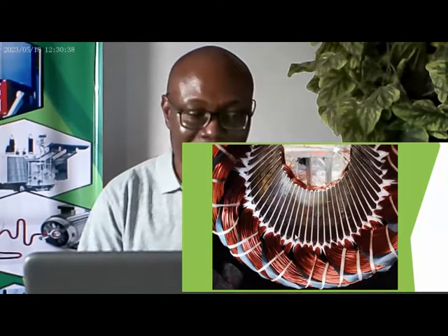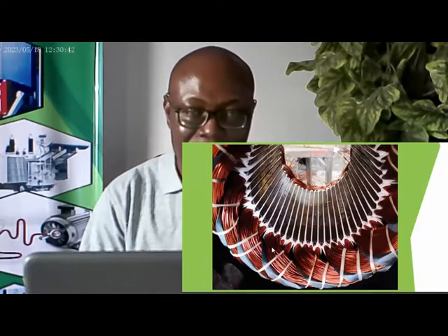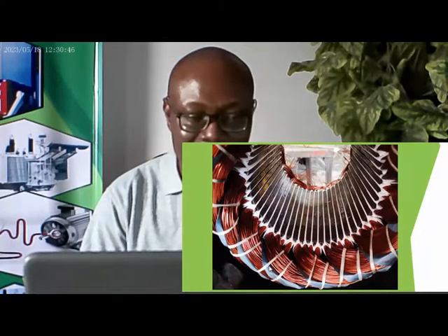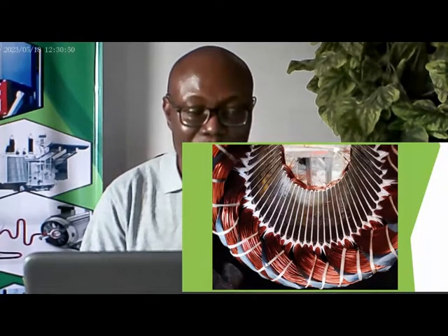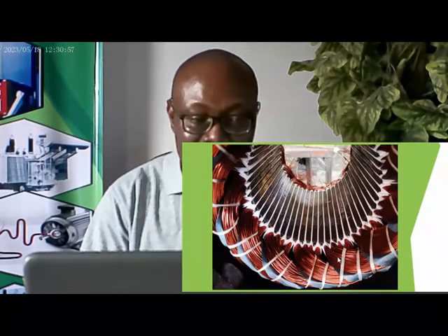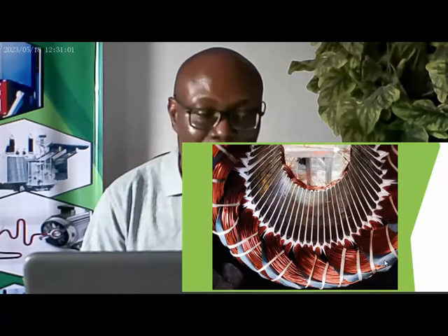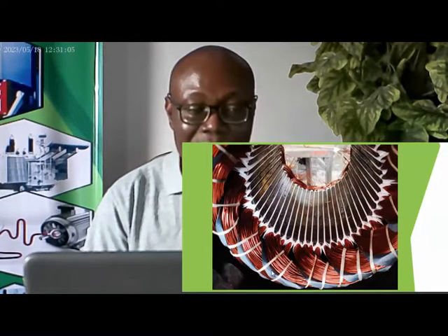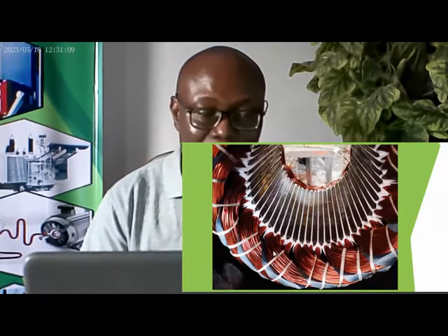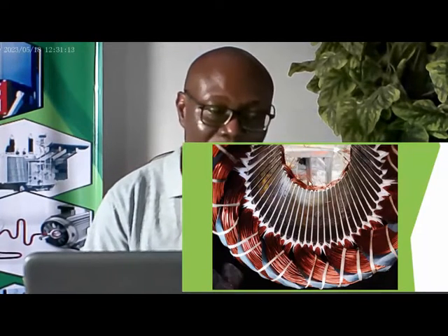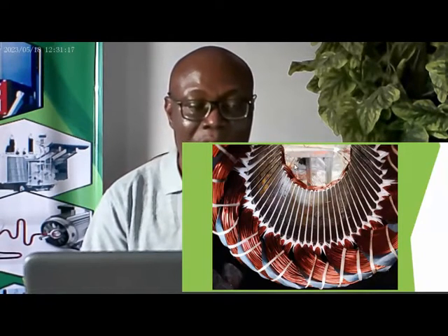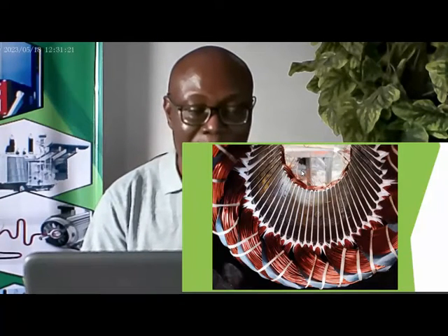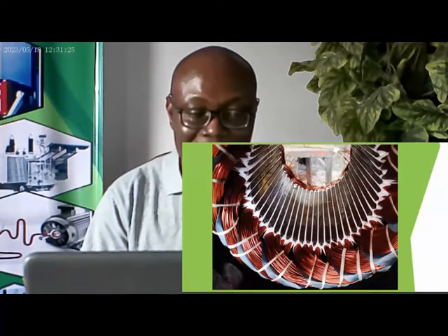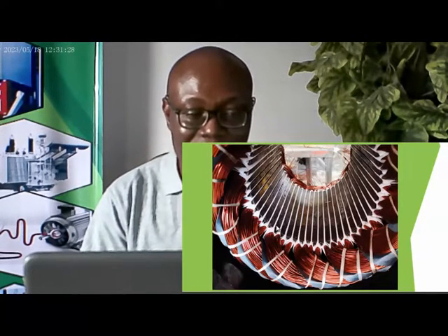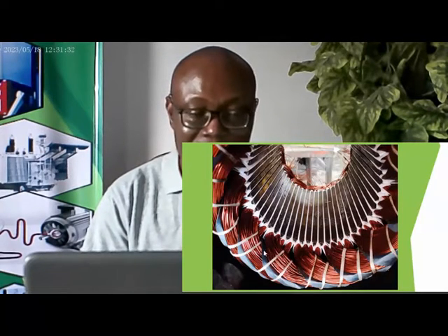If you also look at these windings, you see that there is an insulation, paper lead thread, that is used to separate each of these windings. So this winding does not have any interaction with that winding because of this separation. The windings that will have interactions are those that you deliberately connect to one another on the other side of what you are seeing now. So this coil does not have interaction with ground, and each of the phases of the winding does not have interaction with each other.